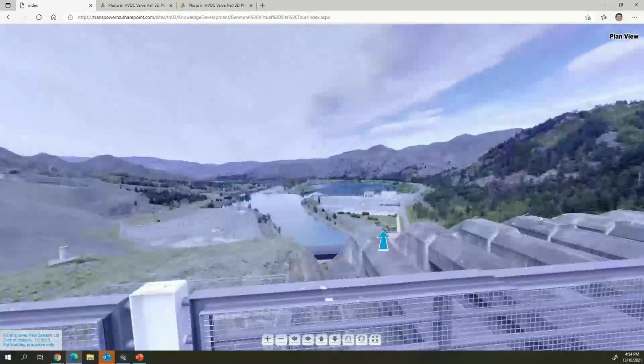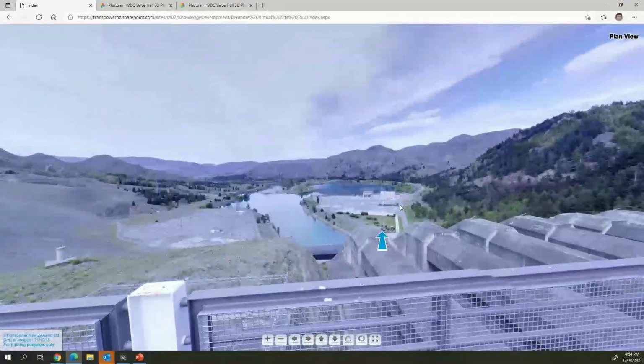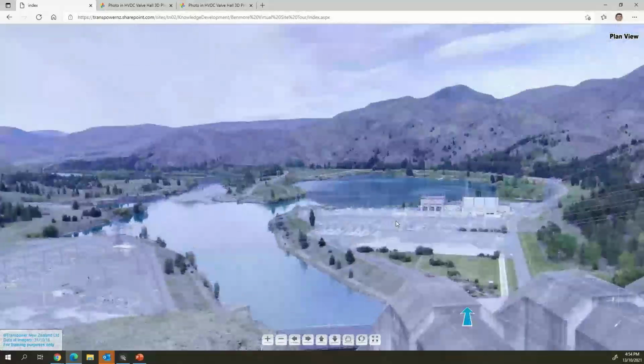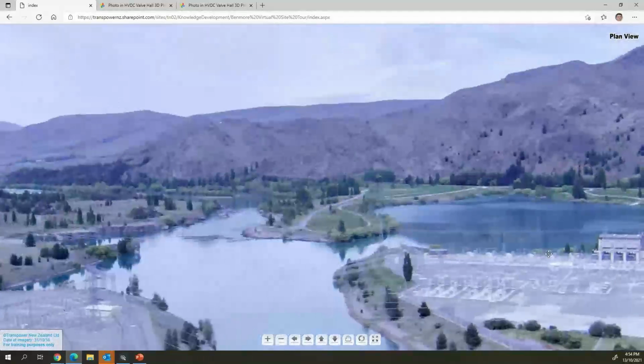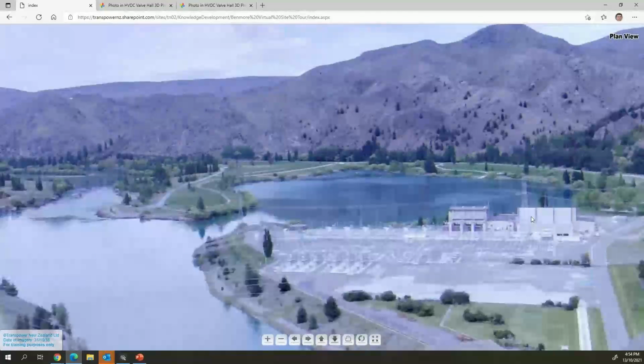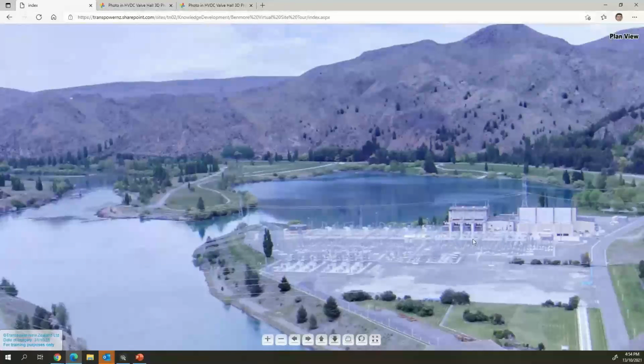Okay, that's great. So this photo is taken on top of the Benmore Dam, so you can see the HVDC converters down here. We've got pole 3 on the right and pole 2 on the left, and all of this gear out in the yard is pretty much AC filters. So you can see how much space you need. All the converters are within these buildings, but we need more than double the space of what the converter halls take up in AC filtering to service the converters.